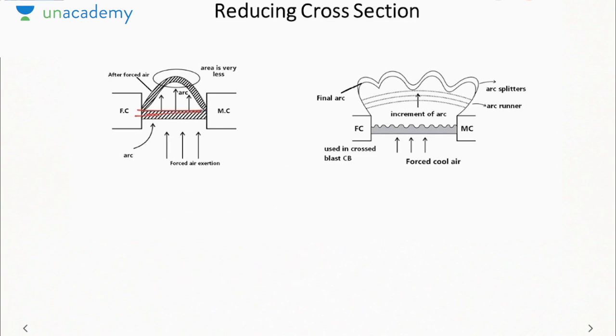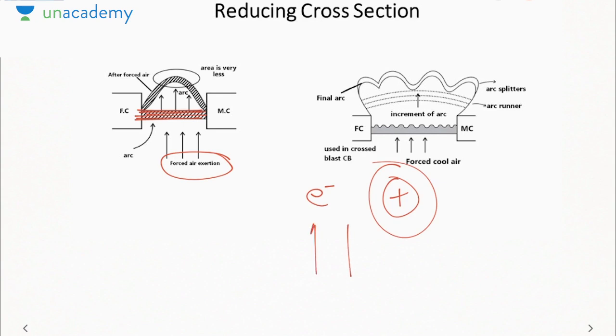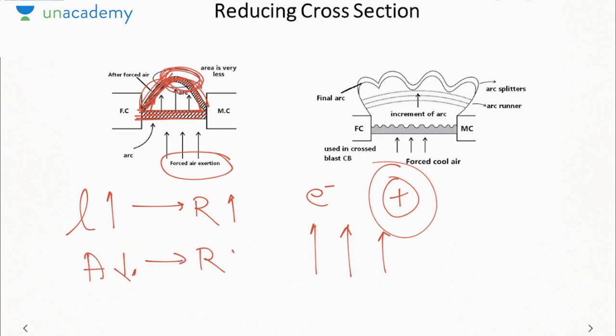Earlier the arc would exist like this between the two plates. Now suppose we push forced air through the circuit breaker plates. Since the arc consists of nothing but electrons and positively charged ions, if you push air, these charge carriers will feel the force and move upwards, due to which the arc will become like this. Now effectively the length of the arc becomes higher. So length increases, due to which resistance increases, and the cross-sectional area reduces, due to which resistance again increases. That is how we reduce the area of cross-section of the arc.